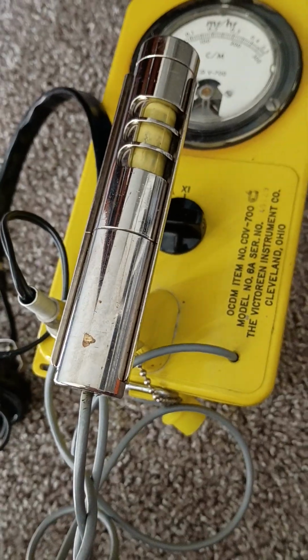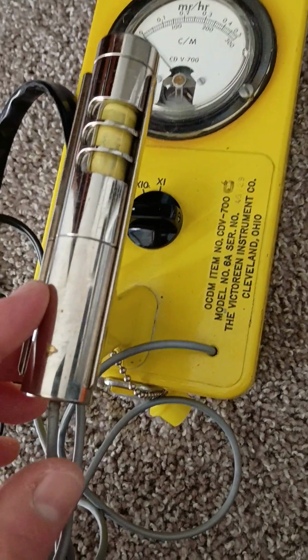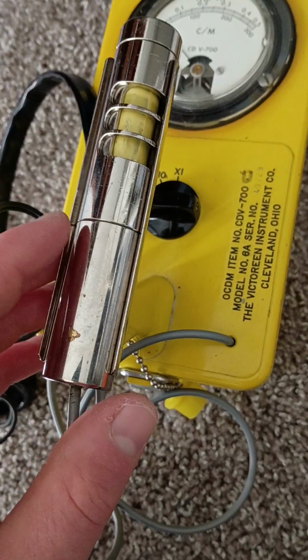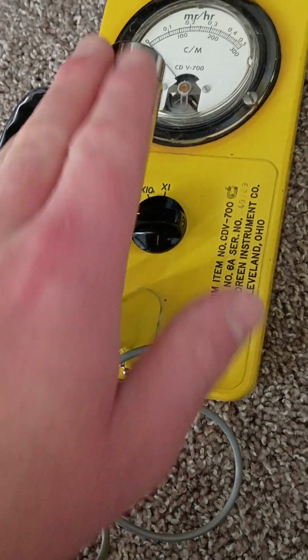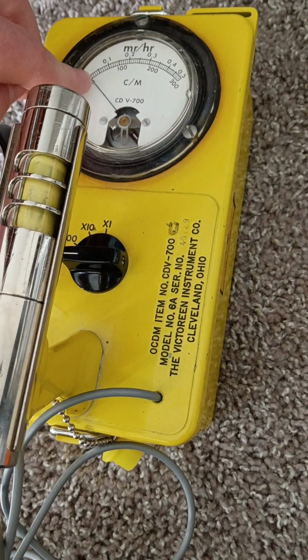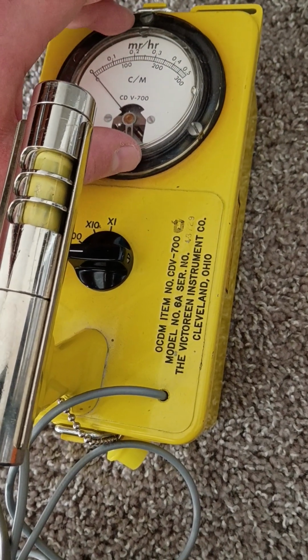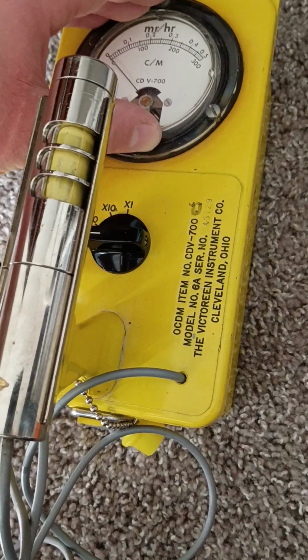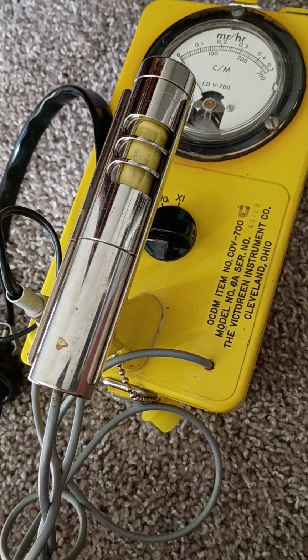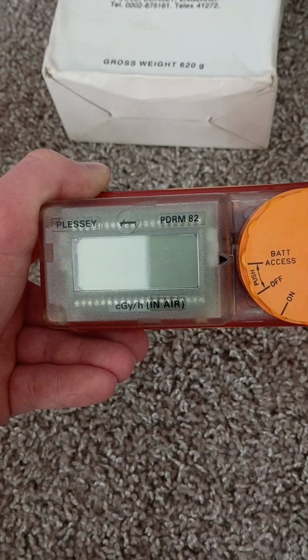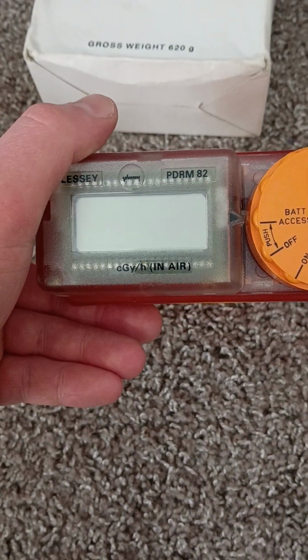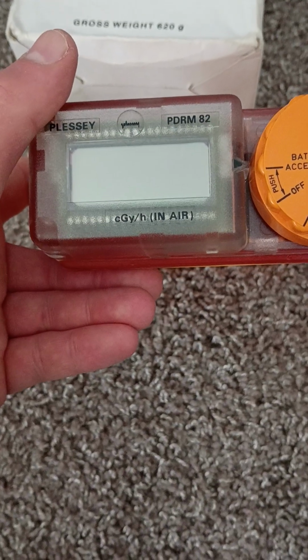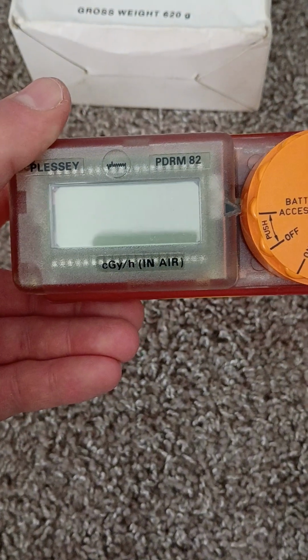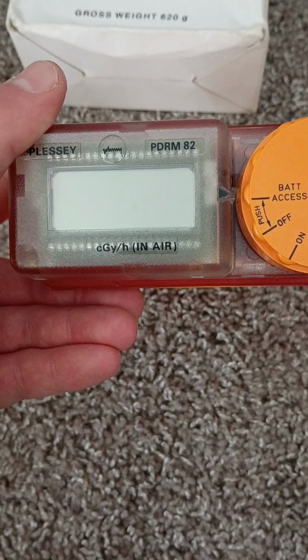There's something called the foldback effect with most Geiger tubes, and that includes this, where if it is confronted with a radiation level that is too high for it, it will actually give false readings, and sometimes it will just go completely back to zero because it is physically not capable of getting readings that are that oversaturated. Whereas this, as a result of some very specialty technology, which you do not see in other Cold War Geiger tubes like the 700, this is a Geiger-Muller-based device, which is extremely high range. We're talking like ground zero after a nuclear weapon was just detonated, high range.